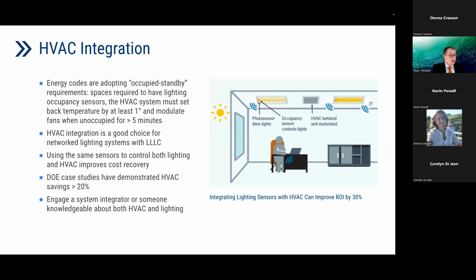It does require someone to actually think about how you communicate between the lighting system and the mechanical system. So it is not a quick, just out of the box. You do need to think through it, but it is very possible to do. There are also energy codes that are now looking at occupied setback. You don't have to do the energy code requirement. It doesn't say you have to do it through the lighting system. They're just encouraging you to look at that.